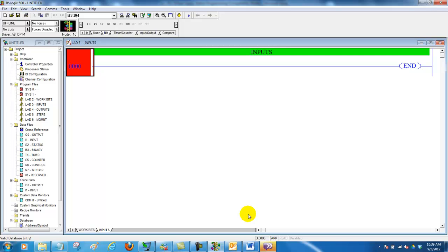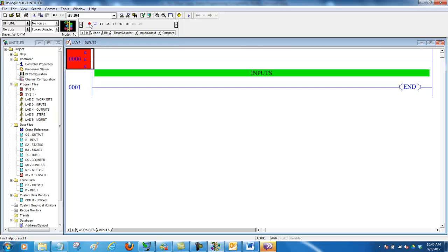Can the transfer cylinder be in two modes at the same time? Can it be extended and retracted? Could it theoretically happen that both reed switches come on? It can? So if both reed switches are on, is it extended or is it retracted? Don't know, do you? Okay? So we need to provide some additional info here to prove if this thing is really retracted. So let's do it. Let's put an input in.